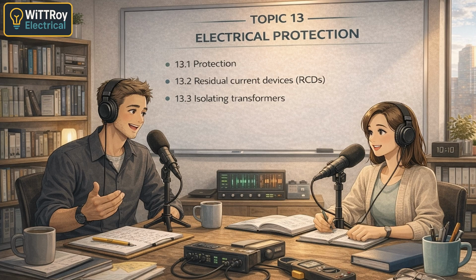Exactly. An isolating transformer has a primary winding and a secondary winding with no direct electrical connection. So the windings aren't physically connected. Correct. The only connection between them is magnetic. Through the transformer core. Yes, because of that, the secondary side is not connected to Earth. We said it floats. Yep, floating secondary. That's an important term. And that floating part is what makes it safer.